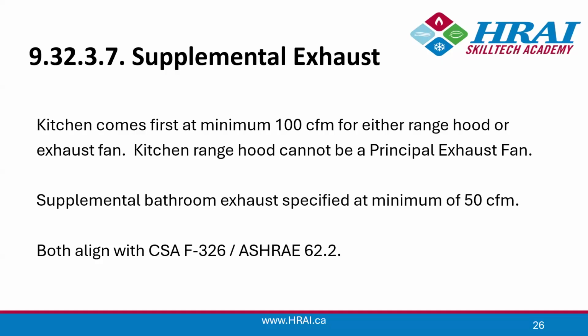Supplemental bathroom exhaust fans are specified as well at a minimum of 50 cubic feet per minute. So there's your two numbers, 50 for the bathrooms, 100 for the kitchen, spelled out for you in this version of the code. Both of these align with the CSA F326 standard as well as the ASHRAE 62.2 standard. So whichever one you look at is all the same now.